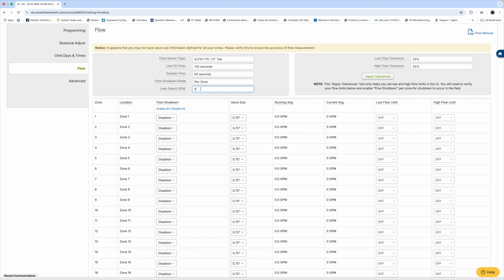And then finally, we get to leak detect. Now, this is primarily for normally open master valves, where your main line is consistently charged with water. So you want to determine what your acceptable level of water usage is if you have hose bibs or quick coupler valves installed throughout the main line. Now, if you have a normally closed master valve, it's still important to give us a positive value here. So you could do something as simple as 3 gallons per minute. That way, if there's any fluctuation within the water captured within the T, as we all know, the earth moves and there's gravity and things of that nature. And so you just don't want to end up with a false alarm by leaving it set to 0. So just put a positive value there.